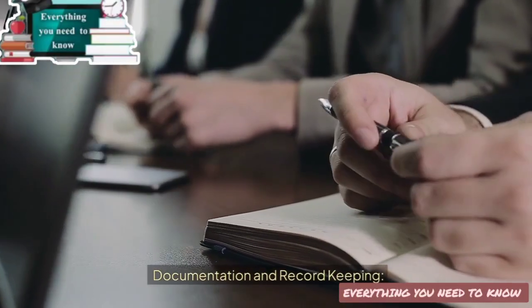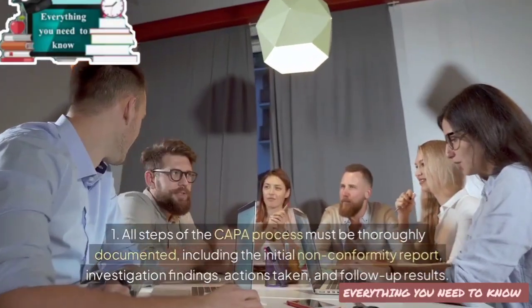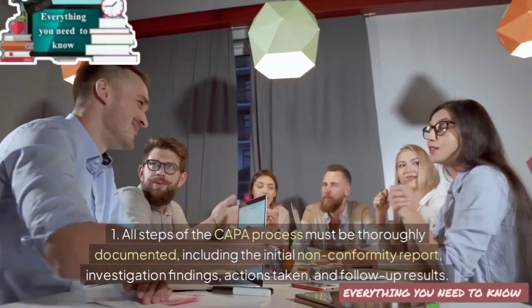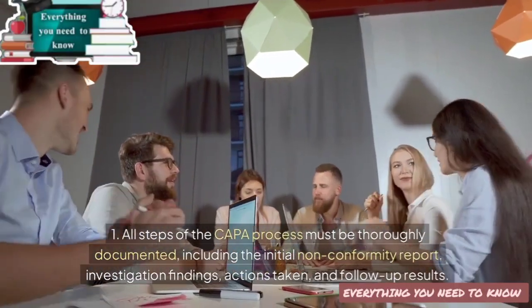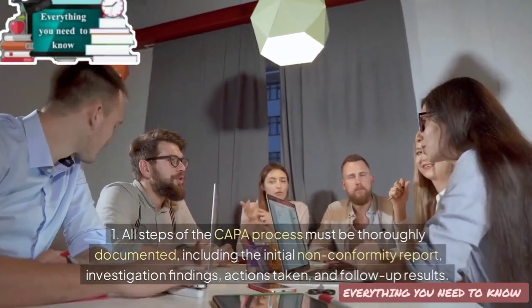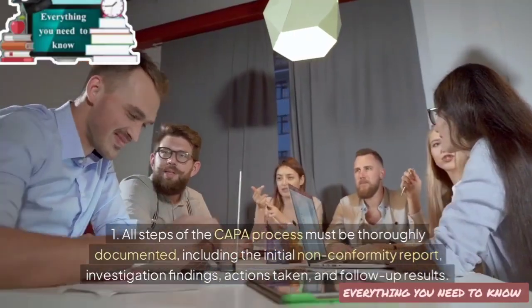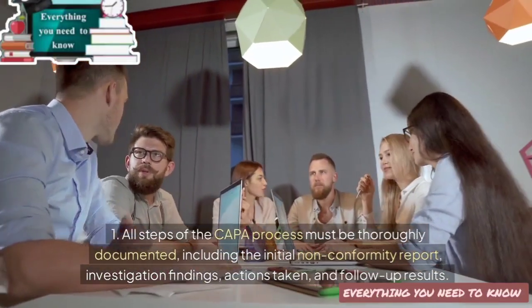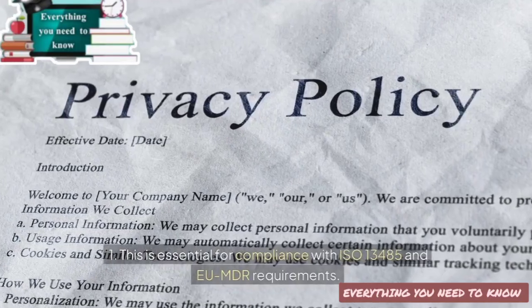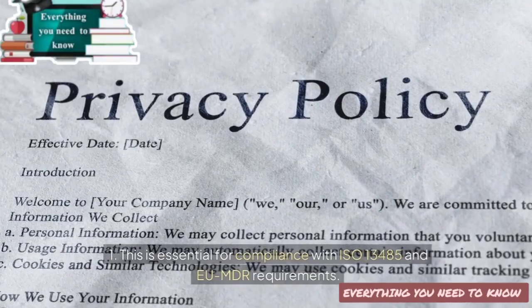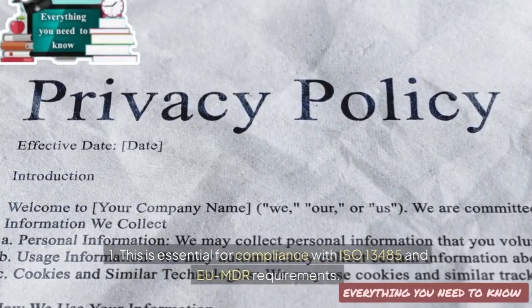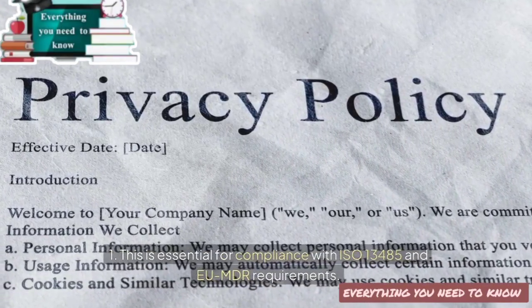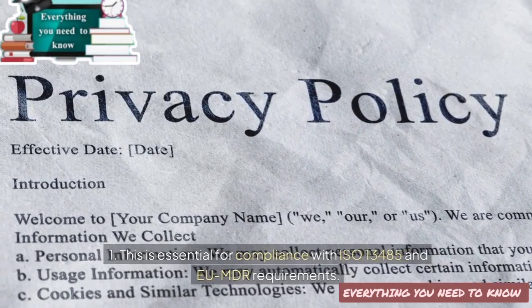Documentation and record keeping. All steps of the CAPA process must be thoroughly documented, including the initial nonconformity report, investigation findings, actions taken, and follow-up results. This is essential for compliance with ISO 13485 and EU MDR requirements.